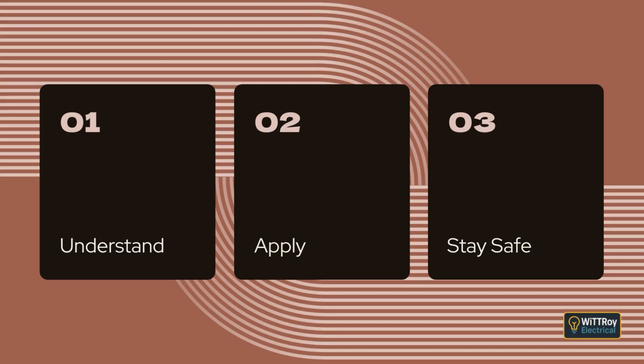Clause 1.5.3.2 Methods of protection. The standard uses two layers of protection. A. Basic protection. Basic protection prevents contact with live parts during normal service. This is achieved through insulation on live parts, barriers, enclosures, or placing live parts out of easy reach. These measures are designed to prevent accidental contact under normal conditions. B. Fault protection. Fault protection deals with indirect contact, where a fault makes exposed metal become live. The main protective methods are earthing, bonding, and automatic disconnection of supply using devices such as fuses, MCBs, and RCDs. The aim is that if a fault occurs, the supply will disconnect quickly enough to prevent harm.